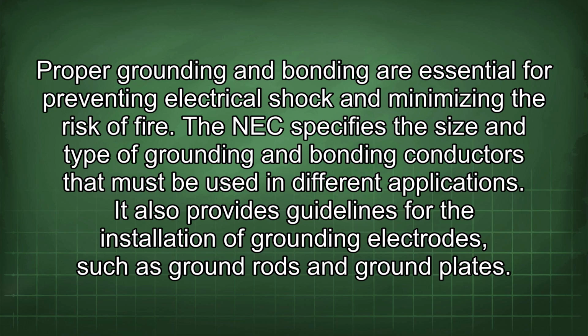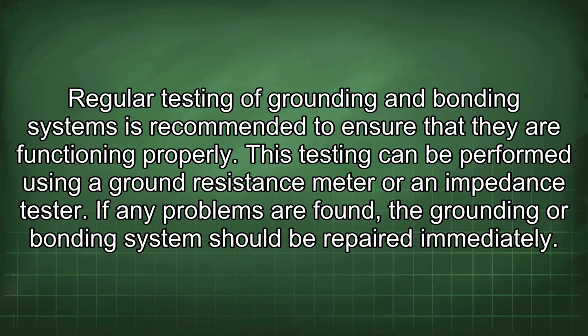The NEC specifies the size and type of grounding and bonding conductors that must be used in different applications. It also provides guidelines for the installation of grounding electrodes such as ground rods and ground plates. Regular testing of grounding and bonding systems is recommended to ensure that they are functioning properly. This testing can be performed using a ground resistance meter or an impedance tester. If any problems are found, the grounding or bonding system should be repaired immediately.